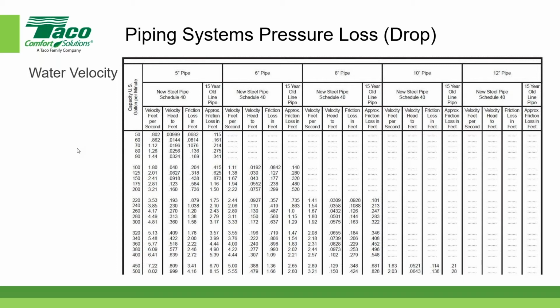Now, if I'm designing a variable flow system, for example, either hot water or chilled water for building heating or cooling, I might actually select my pipe size based on 10 feet per second, knowing that in a variable flow system, the velocity very rarely runs at 10 feet per second, because the number of hours in a year that you wind up with peak load is very, very small. It's probably less than 1%. And so you never really reach the full flow in gallons per minute for the overwhelming majority of hours. So in variable flow systems, I tend to use a higher velocity.